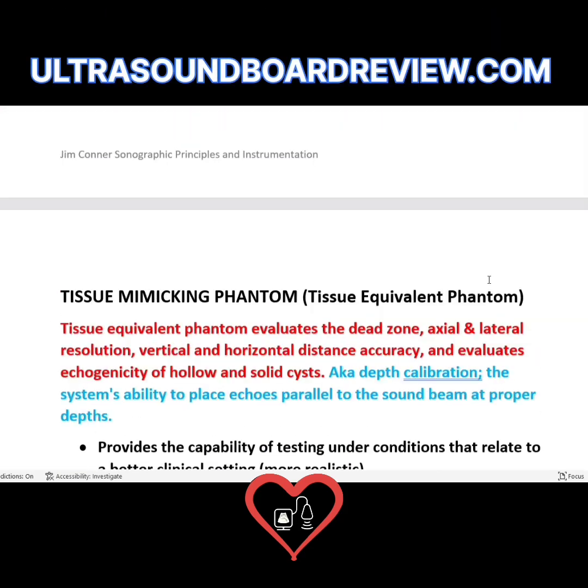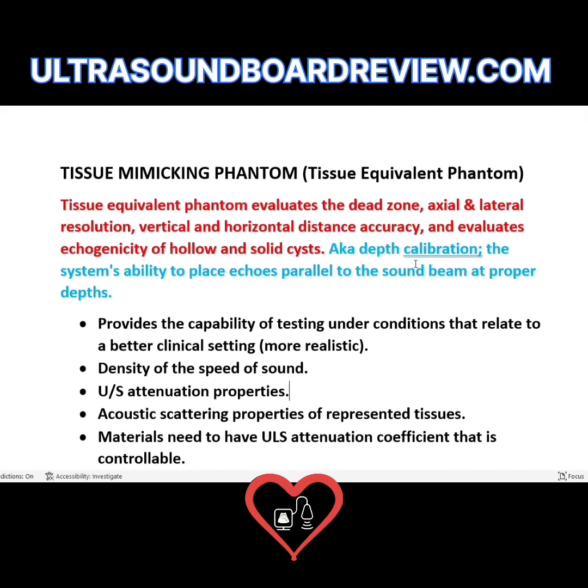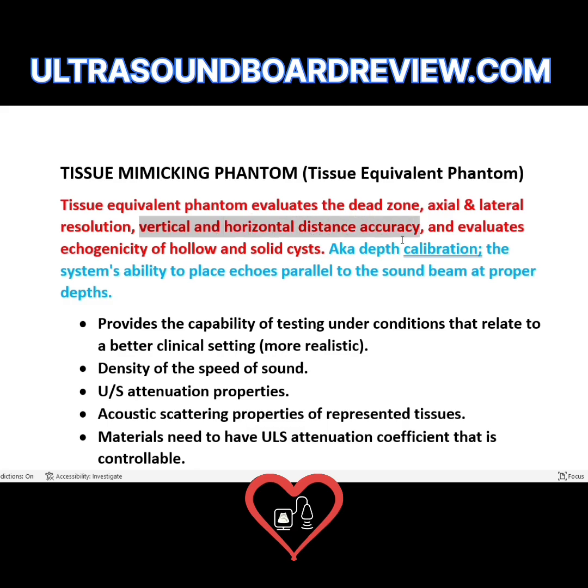There are different types of phantoms. The first is the tissue mimicking phantom — just like the name says, it is the closest we can create to actual tissue. You need to write in your notes that this evaluates not only the dead zone, but axial and lateral resolution, the vertical and horizontal distance accuracy, and the echogenicity of hollow and solid cysts.